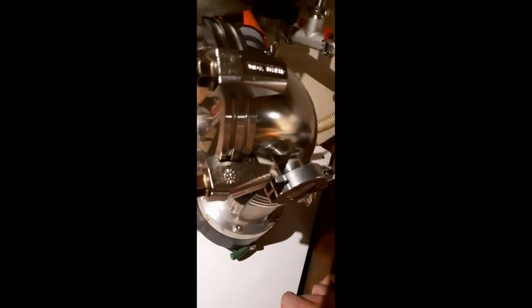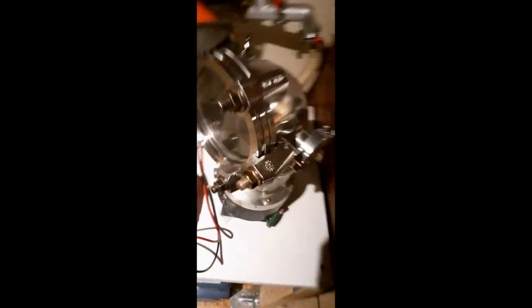So last time I made an update on this, I had just gotten a turbo pump and some other vacuum hardware, and now it's pretty much done. So first of all, there's a roughing pump here. This is a two-stage rotary vane pump, and it just has a reinforced hose going up behind this system here to a shutoff valve. Everything between these two pumps is called the foreline, so it has a shutoff valve here so I can isolate the two. This is very good because otherwise if this suddenly stops, or the pump stops, it can suck oil back in.